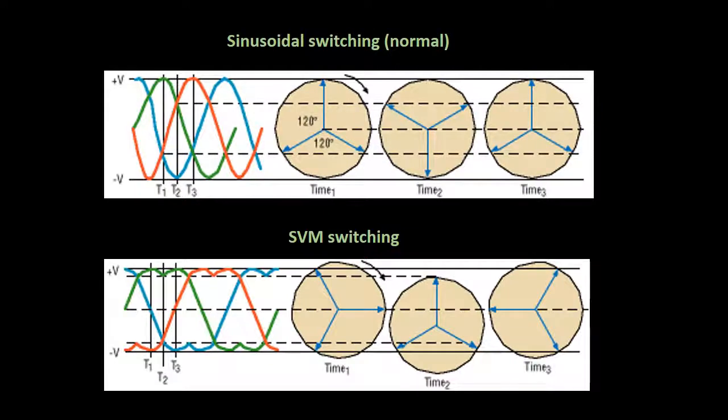You may also consider using more efficient switching patterns, such as space vector modulation, over the standard sinusoidal modulation. Without going into the specifics, certain switching patterns can improve a VSD's total harmonic distortion and efficiency, as well as being able to cope better with varying loads.